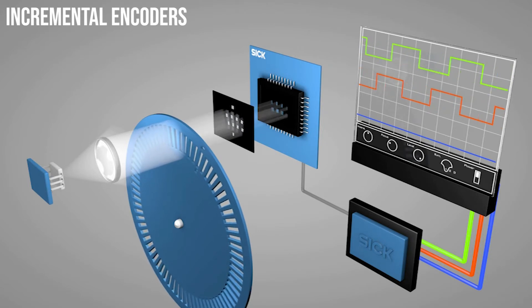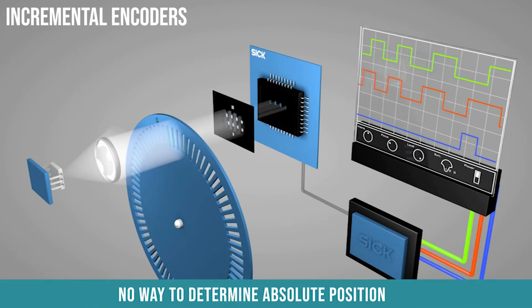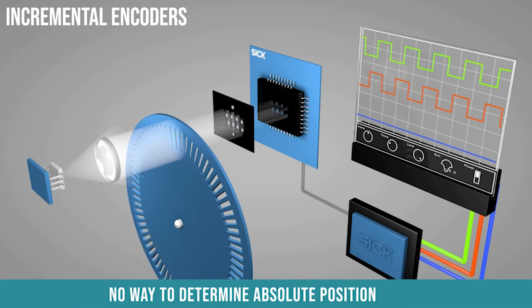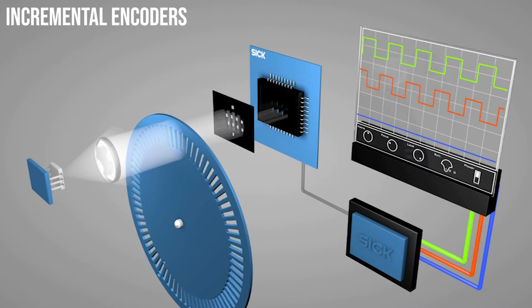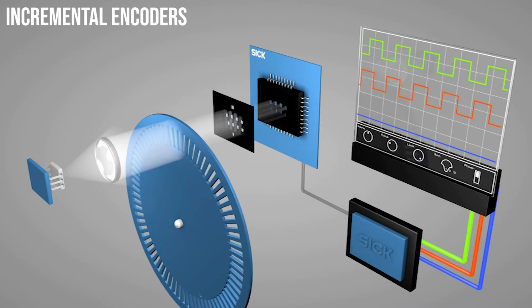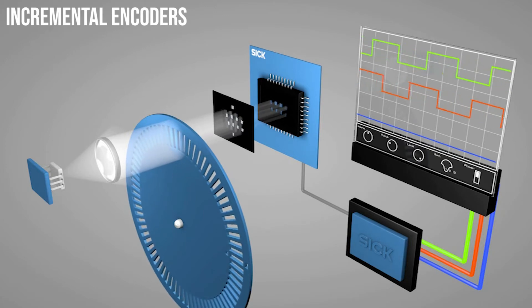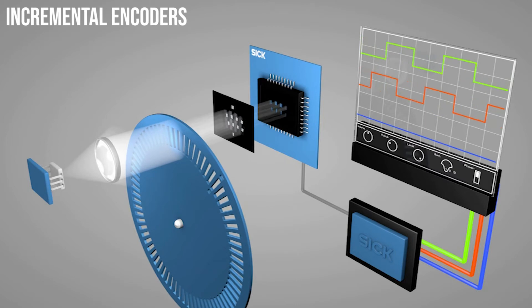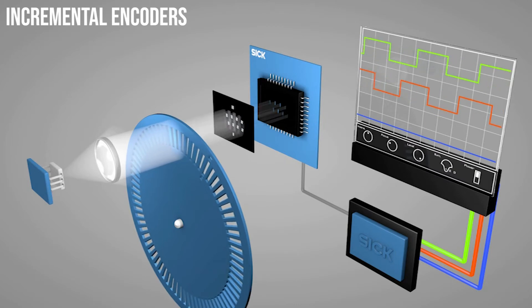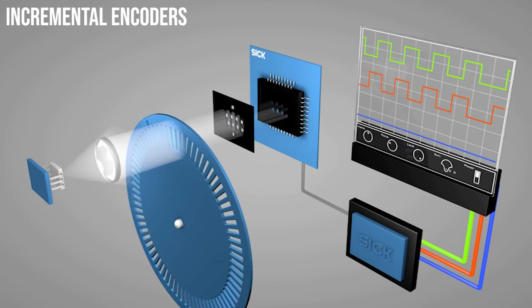The downfall to an incremental encoder is that there is no way to determine absolute position since it is just measuring incremental movements. For example, say this encoder was powered off. When the system came back on, there is no address or indication of where the encoder disk is in its rotation. This means that the zero or home position is lost when power is switched off and it must be reset when the encoder is powered back up.